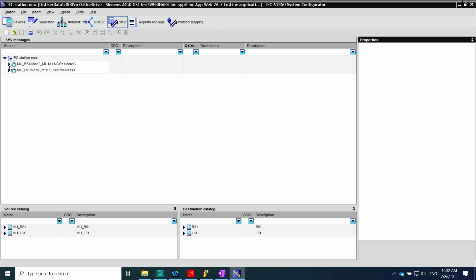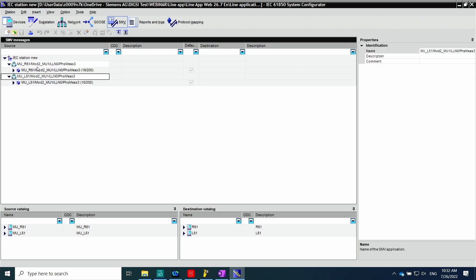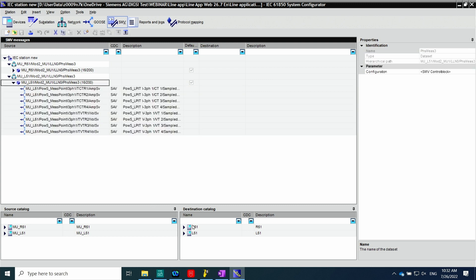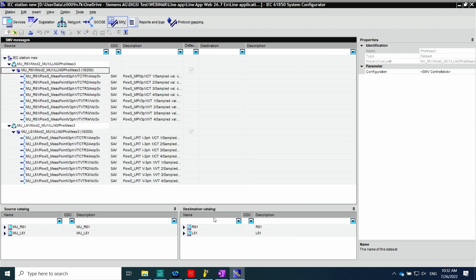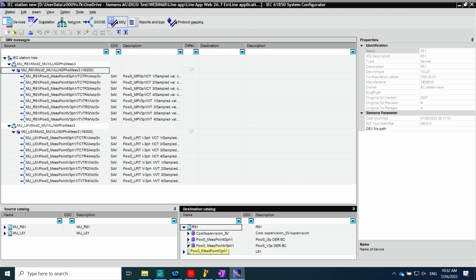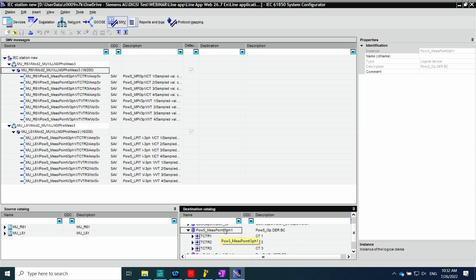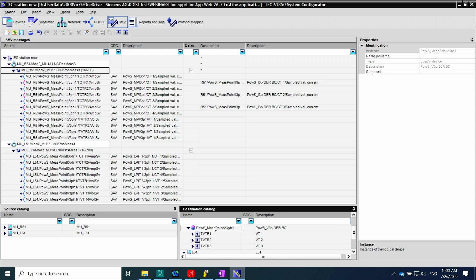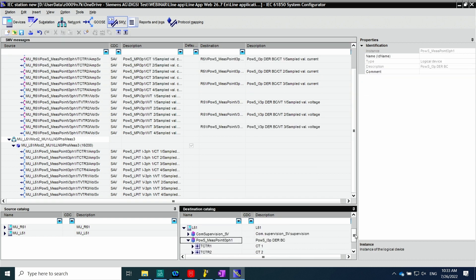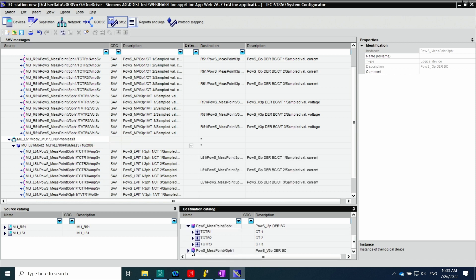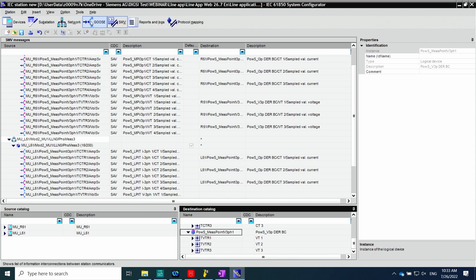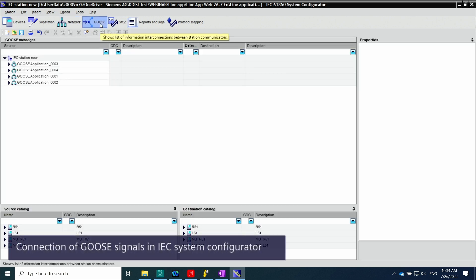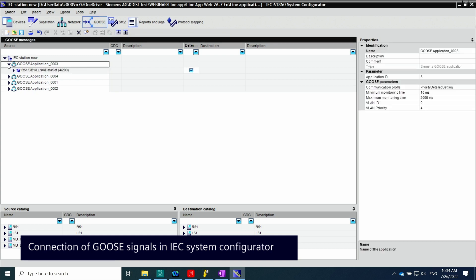On sampled measured values, there are two merging units that will publish the information: MU R51 and MU L51. Two clients are present — R51 receives information from the conventional transformer and L51 receives information from the low power instrument transformers. First, the connection between merging unit R51 and relay R51 is made using the destination catalog. The device R51 is expanded, looking for the current measuring point, and then connected to the merging unit using drag and drop. The same is made for voltage. The connection for R51 is done, and the same procedure is made for relay L51 on the left side.